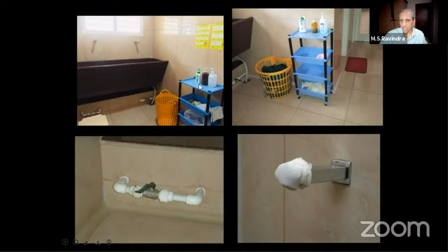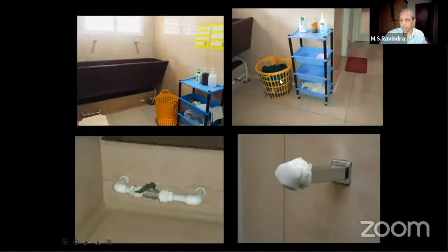The scrub area has to be very clean. There should not be any crevices between the tank and the wash area, wash bay and the walls. Many times we put a steel one, there will be a lot of space there. That space is very rich in fungus. So this has to be avoided, and nothing should be on the wall. The wall should be absolutely clean, and all the scrub things are on a separate trolley, which can be easily moved. When you discard the gowns, they should be kept in a porous bucket so that the wet areas in the gown will not multiply organisms.